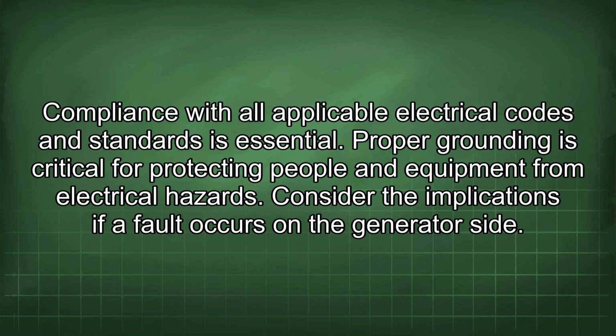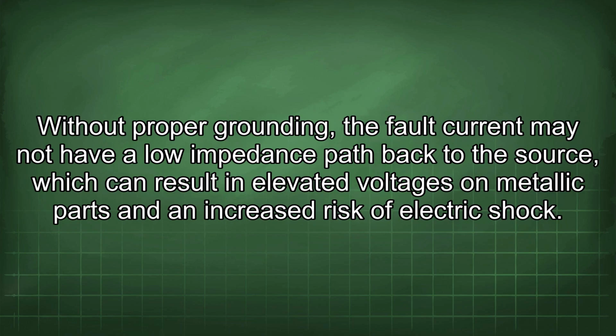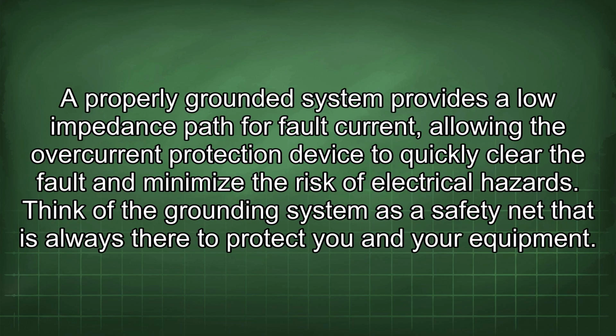Consider the implications if a fault occurs on the generator side. Without proper grounding, the fault current may not have a low impedance path back to the source, which can result in elevated voltages on metallic parts and an increased risk of electric shock. A properly grounded system provides a low impedance path for fault current, allowing the overcurrent protection device to quickly clear the fault and minimize the risk of electrical hazards.